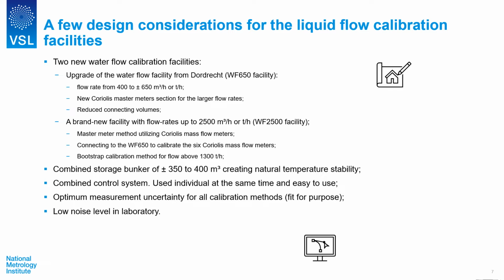And the second facility that we will build is a brand new facility for flow rates up to 2500 cubic meter per hour. So we will call the WF2500 facility. The master meter method will be utilized there with Coriolis mass flow meters. We will connect the 2500 system to the 650 system to calibrate the 6 Coriolis mass flow meters that are in that facility. But we cannot reach the 2500 cubic meter per hour, so we need to bootstrap the 4 largest Coriolis meters with each other to go for flows up to above 1300 tons per hour.